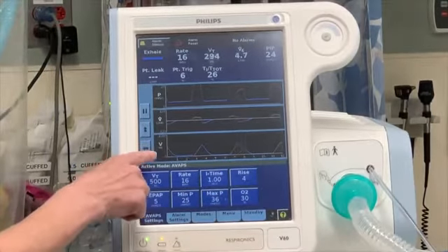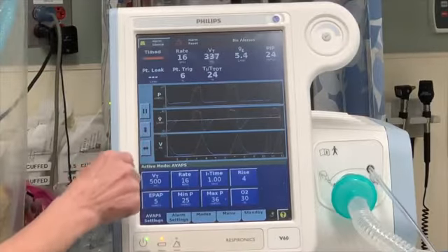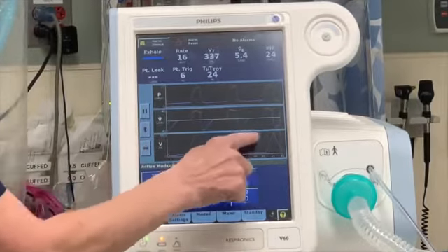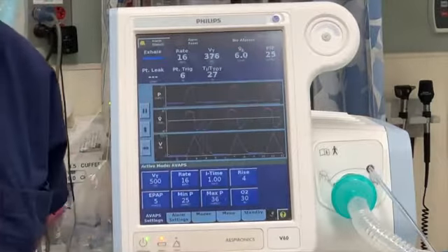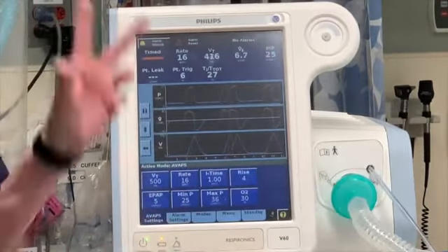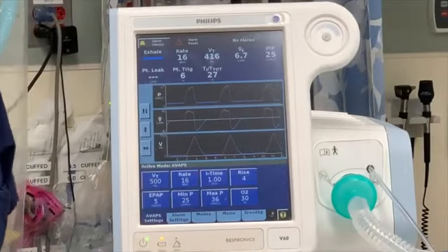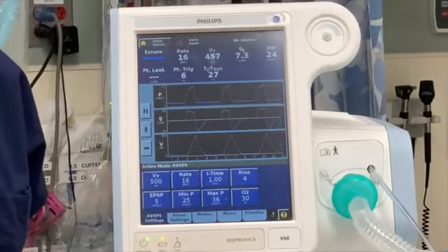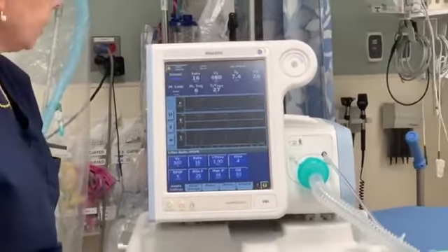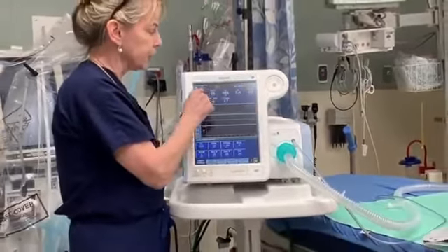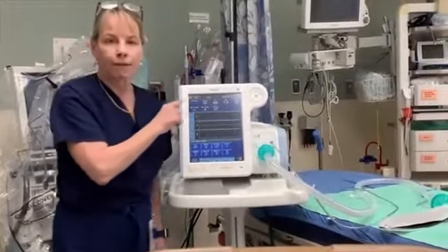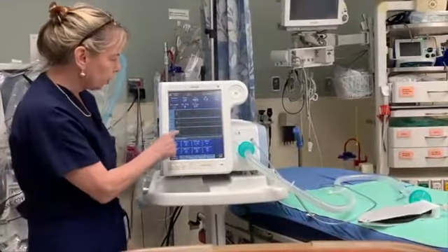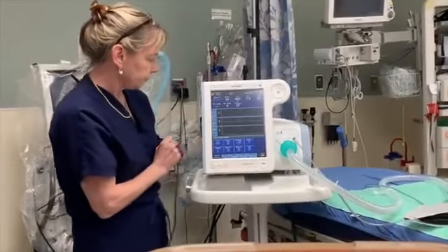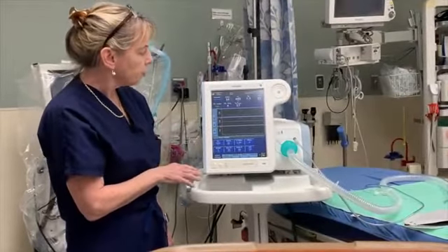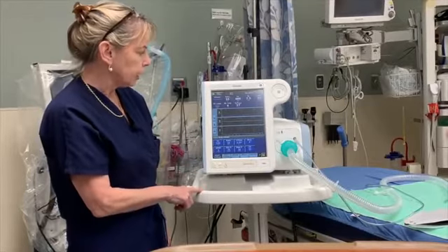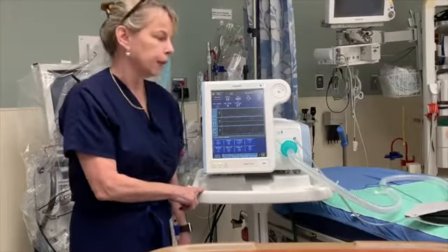So now you can see here, this is 1,000 milliliters at the top. I'll take it like that. You can see it's 550. It's getting adequate volumes. Peak pressures are 24, all fine. And this is in an ARDS type test lung that technically is in a paralyzed mode because it's not breathing on its own. Now, one thing you have to be careful of is interpreting these numbers up here. These numbers are the average over the last 6 breaths. It's much better to look here to make sure you're getting adequate tidal volumes. So that's how you can modify one way a Bi-pap machine into a machine that can provide ventilation.